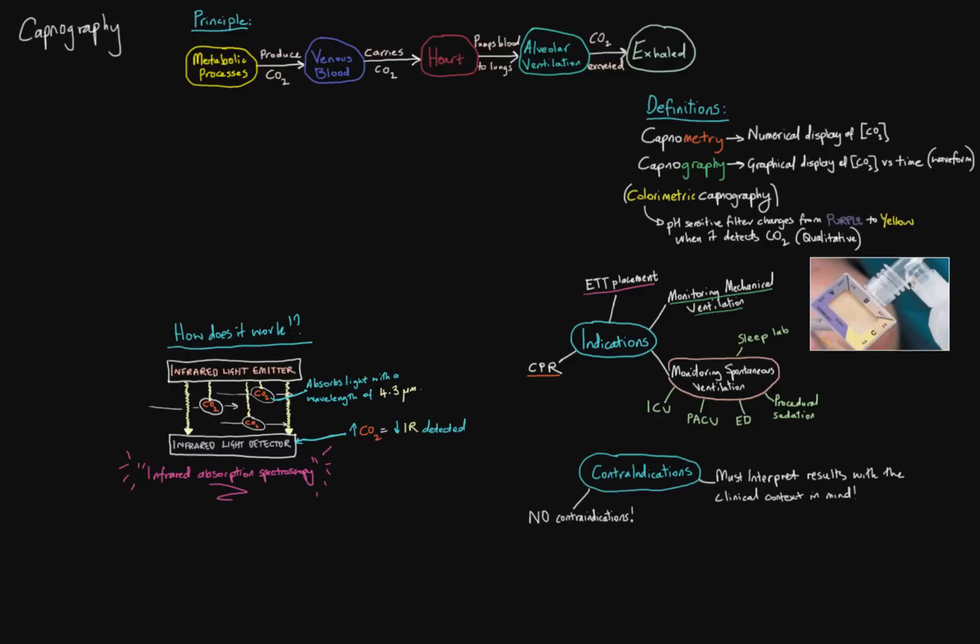Now, there's a couple of ways that these can be applied to the patient, and I'll use the example of an intubated patient here. So this is something that I drew quickly earlier, and you'll see that the main two ways that we utilize this absorption spectroscopy is either through mainstream analyzing or inline and then side stream analyzing.